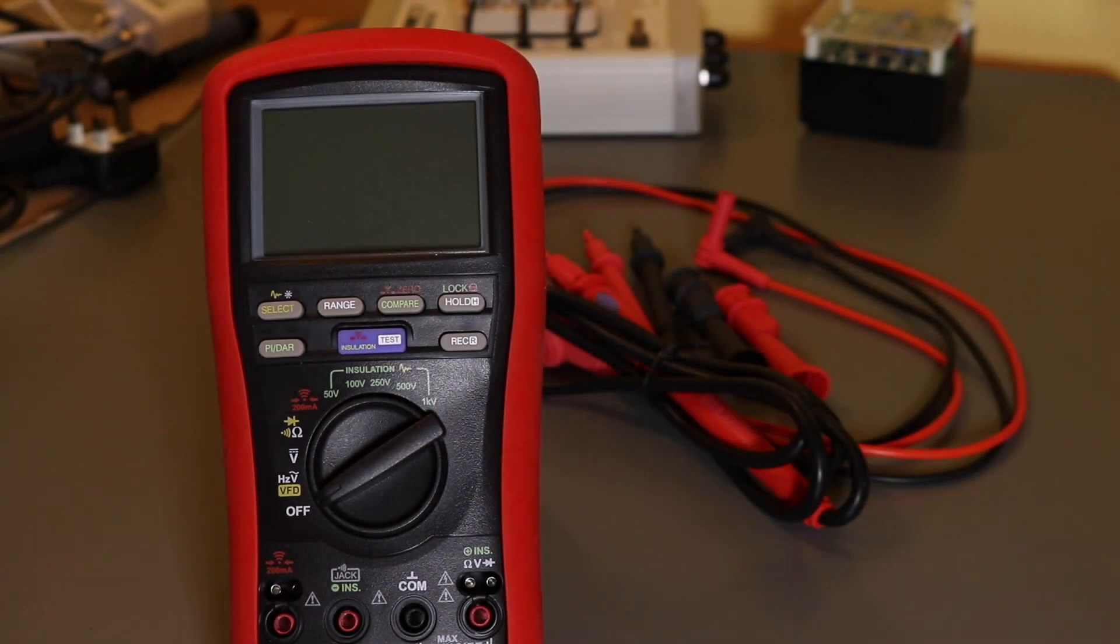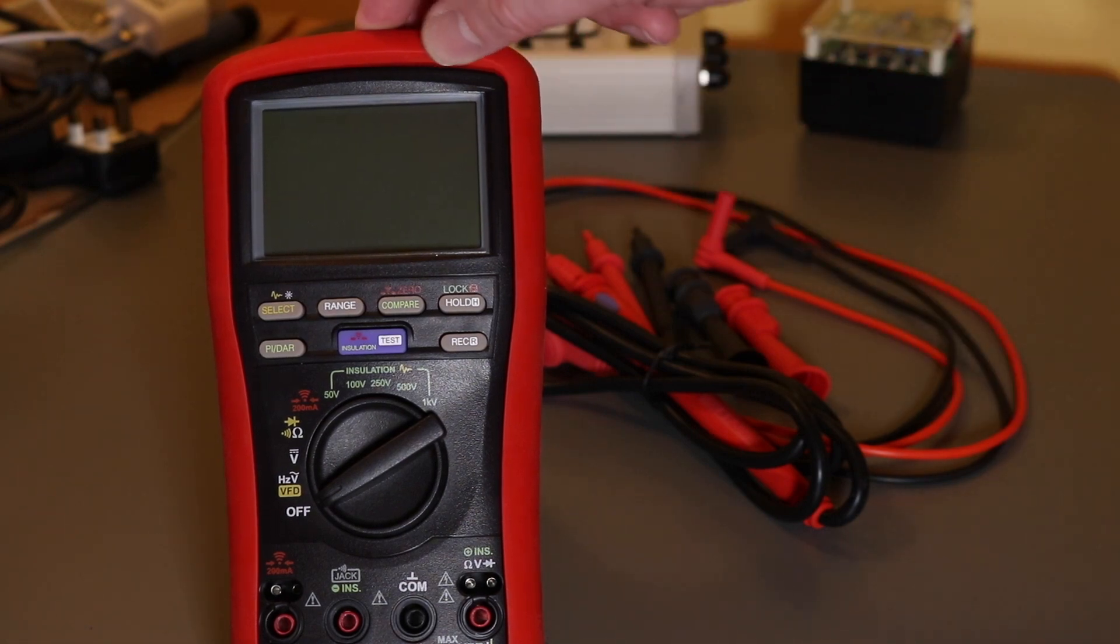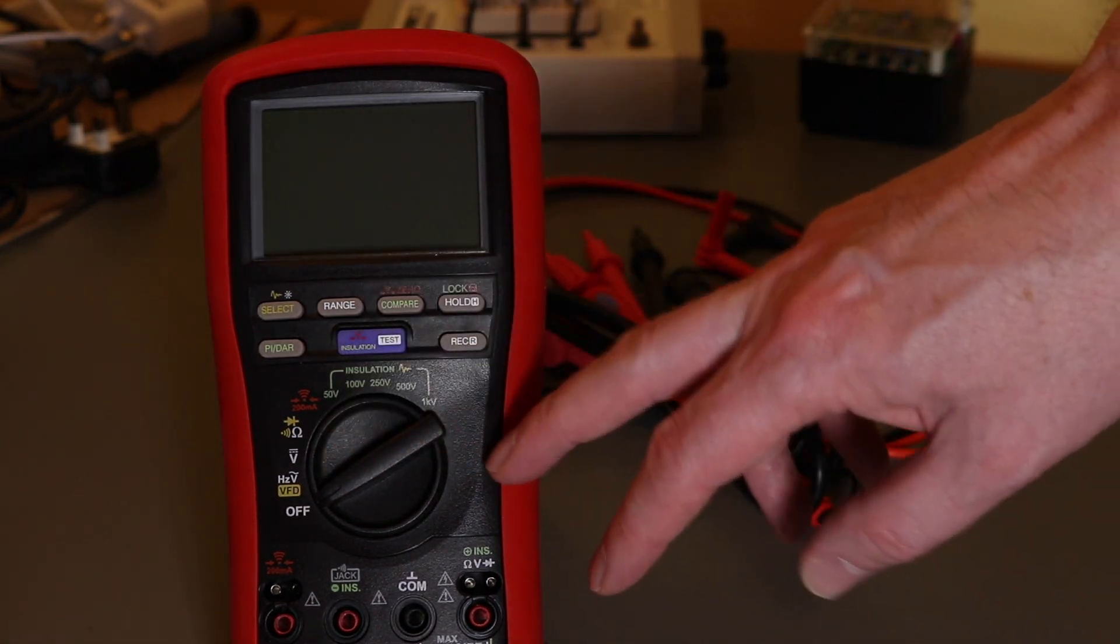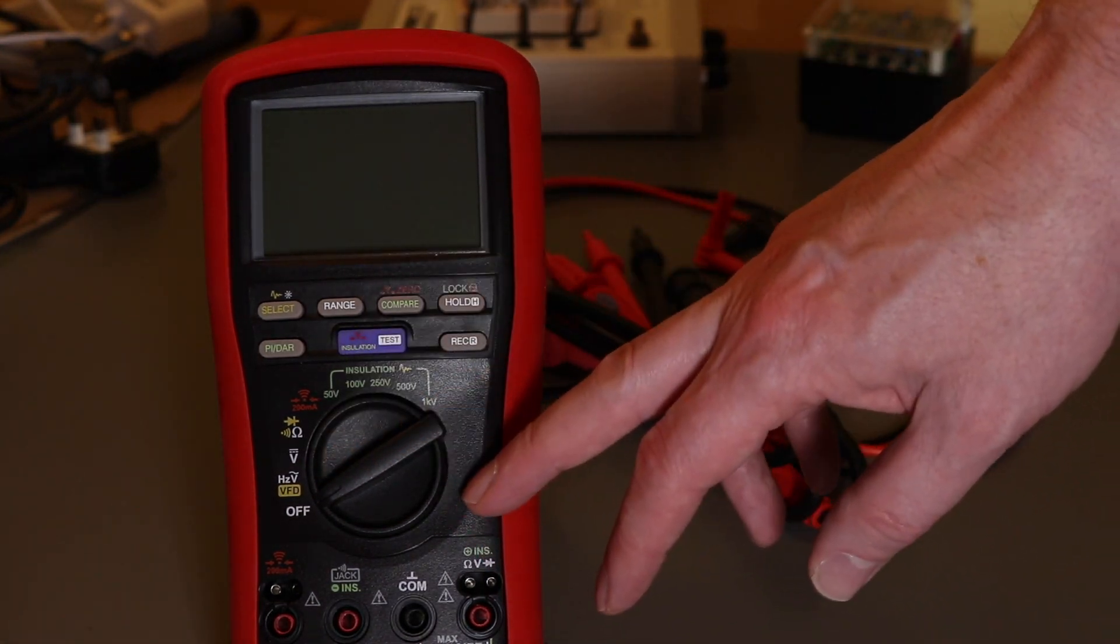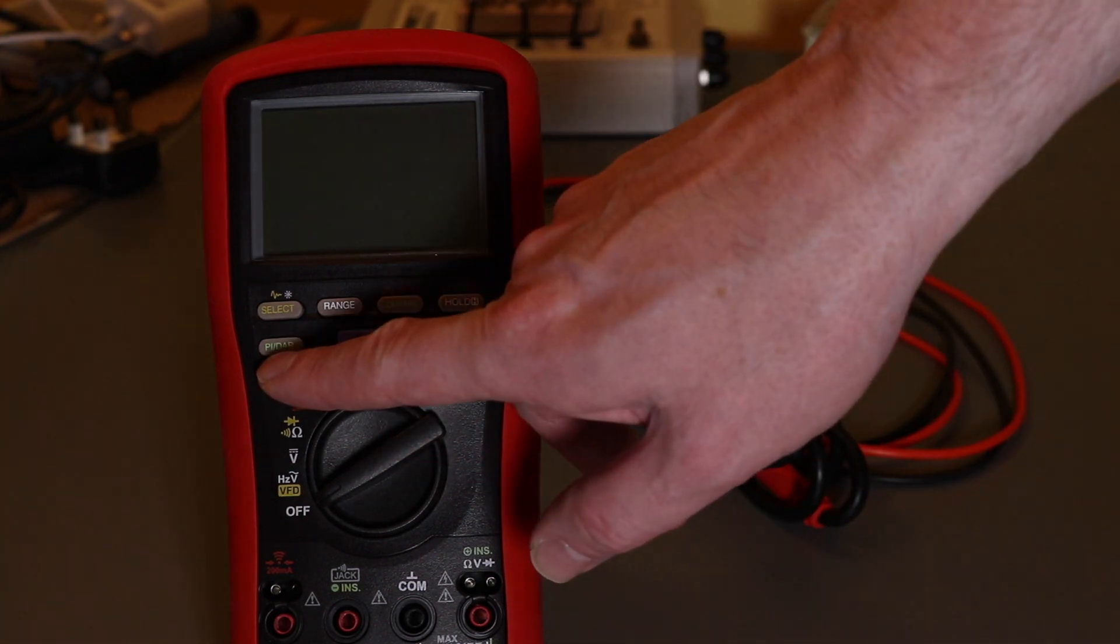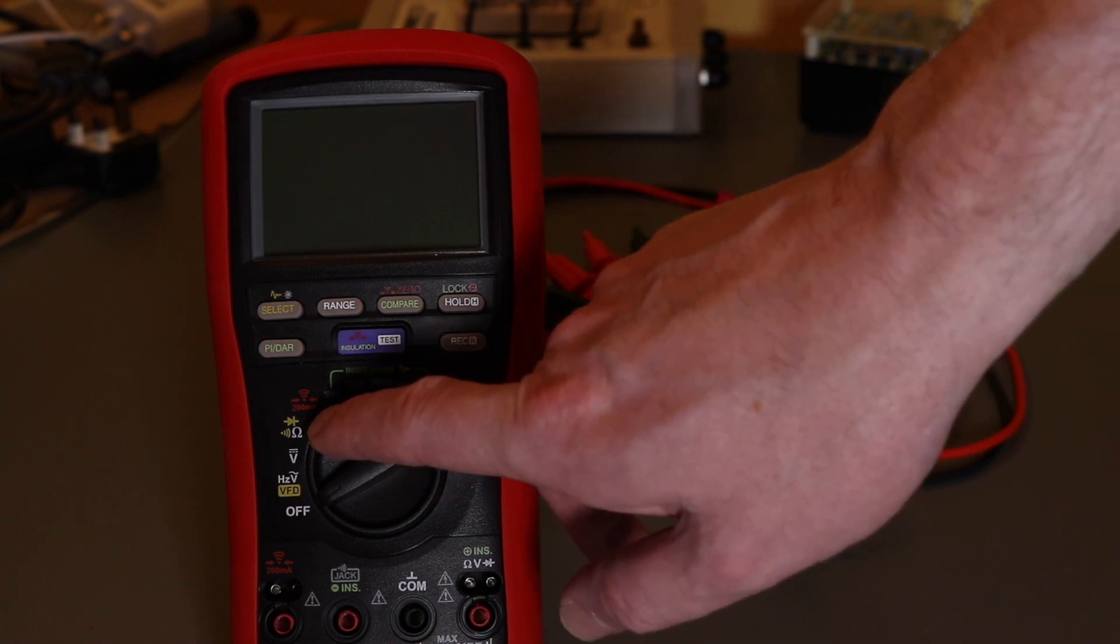Some of the other meters, including ones that Brymen themselves do, have better multimeter functions. However, this is the only meter that they do that has both the DAR and PI functionality along with the earth bond test at 200 milliamps.